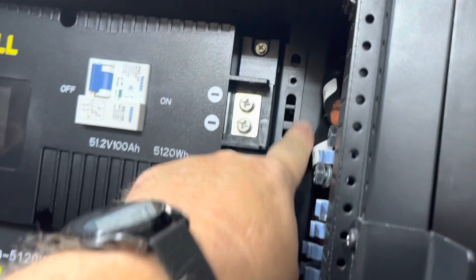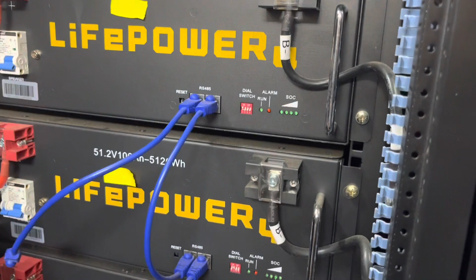Now, there's a ground lug on this particular battery, but none of the other LifePower 4 batteries have a ground lug. So it's really important that you get these screws mounted into the frame, into the rack, because that's your ground connection to ground the can on this LifePower 4.